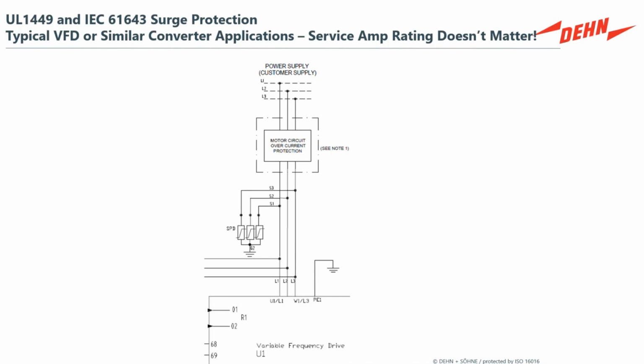The surge protection is rated by voltage and available fault current. Those are the ratings that really make the biggest difference. In the horse race of surge protection, bigger is better, but that's not the case for what's needed. Bigger might be great if you want it to last longer in the application, but it's not how it's rated by the electrical principles.